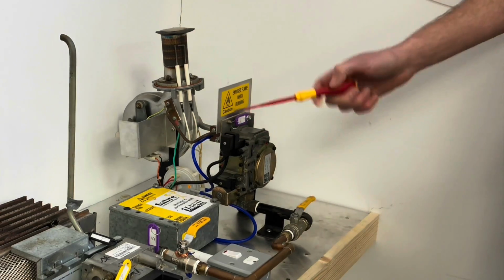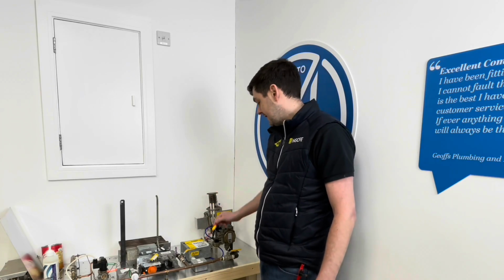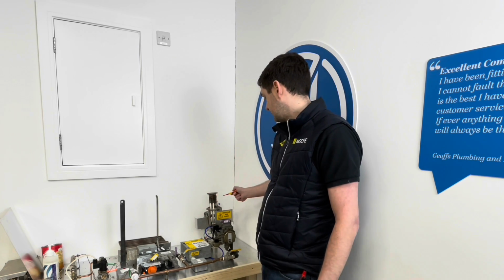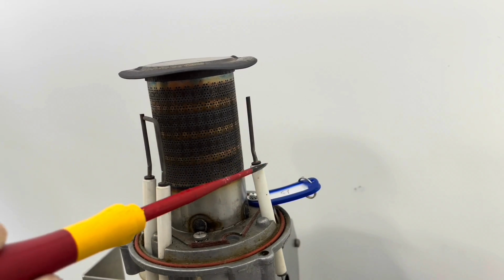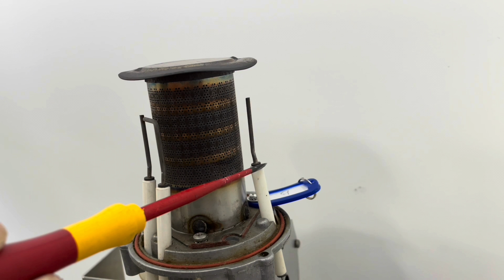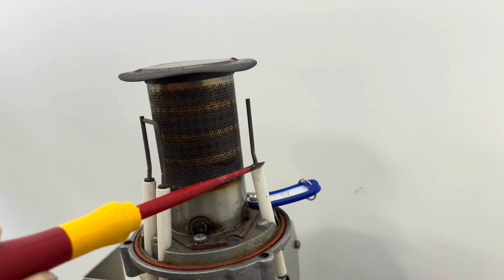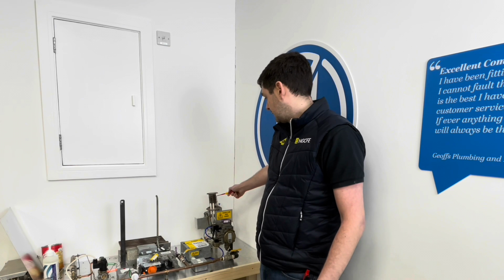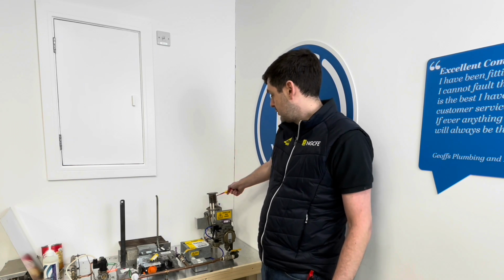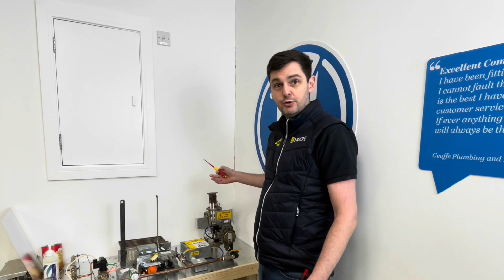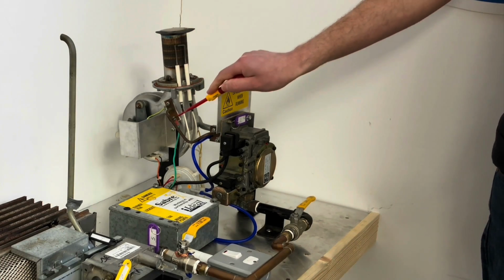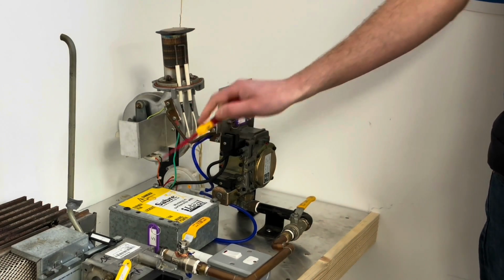So when we turn this igniter on, what will happen is the 100 volts roughly AC current will be present at the flame rectification probe. The burner will light. The voltage will travel through the flame, converting itself to DC current, and will travel back to the board via the green wire here.